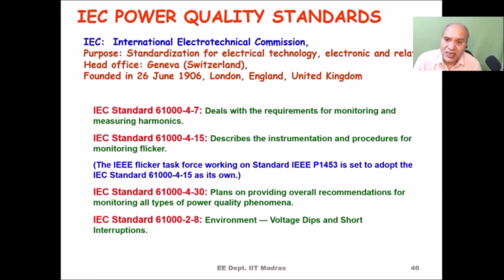Apart from that, there is the IEC, the International Electrotechnical Commission. Its head office is in Geneva, Switzerland. It was founded in June 1906 in London, UK. So the IEC is another agency which sets standards for the operation of the power system. For power quality, we have these important standards: IEC 61000, which deals with the requirements of monitoring and measuring harmonics. IEC 61000-4-15 describes the instrumentation and procedure for monitoring flicker. Then it has various parts like 4-30 and 2-8, which give overall recommendations for monitoring all types of power quality phenomena, and IEC 61000-2-8 describes unbalance, voltage dips, and short interruptions.